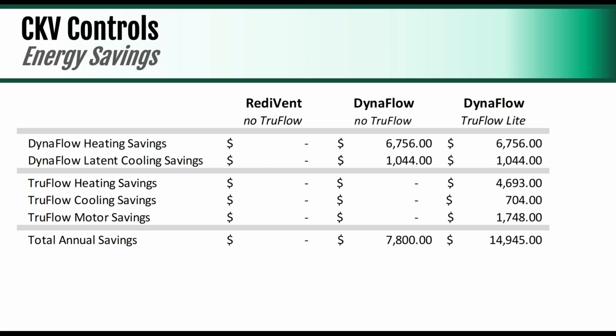So in this project, what we did was we specified TruFlow Lite. And again here, now we've got the heating and cooling savings, and that is, again, the same on both Dynaflow with regular control, so a big on-off switch, or with the demand control system. And this is where, because we're modulating here, we've got additional savings. We've got an algorithm in the system based on all the existing projects out there to show how much savings we're generating.